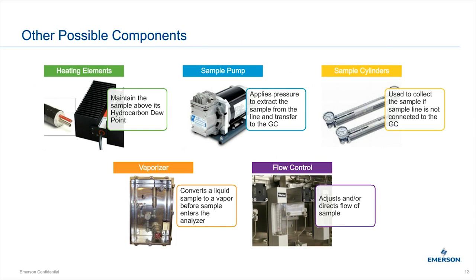Other components include heating elements — for C6+ applications in most of the US you'll need heat tracing and possibly a heater in the enclosure to maintain your position on the phase diagram. Sample pumps may be needed if you don't have enough pressure to get the sample from the probe to the GC over long tubing distances. Sample cylinders are available for grab samples — we can make recommendations. Vaporizers convert liquid to gas for liquid sample analysis; you need to be careful about volume going in, as too much means not all liquid will vaporize, and fractionation can occur.